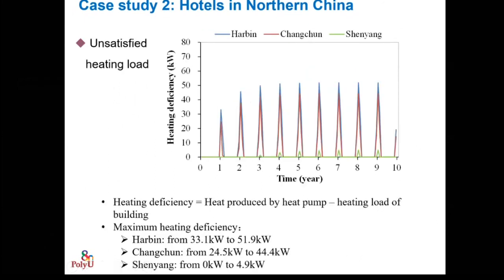So don't always try to use a ground coupled system in very cold weather areas or very hot weather areas, like Harbin or like Hong Kong and Guangdong area in China. The COP could be very low because of the imbalanced heating and cooling. This is the heating deficiency at the three places—Shenyang is much better.